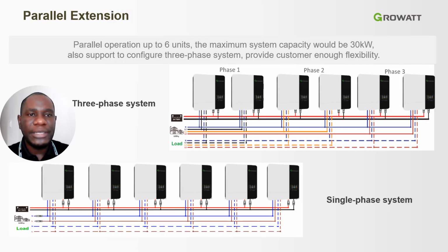Then this is how you can scale these solutions or these systems up. You can put them in parallel. These inverters take up to 6 units per system, meaning that you can go to a maximum of 30 kilowatt per system. They also support single phase and three phase. As you can see, the top part of the diagram shows the three phase system. Depending on the requirements of the client, you just change the configuration or the setup of the inverters. As you can see, the first two inverters represent phase 1, the second set of inverters represent phase 2, and the third set represent phase 3. Then the bottom part of this diagram is showing you the single phase system with your live and neutral and the earth, of course.